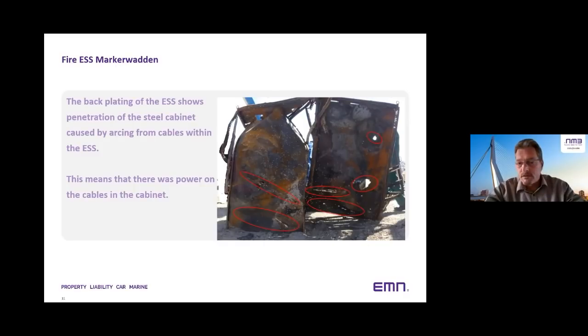This meant for us that there was power on the cable, either from the site itself or from the batteries, which we did not determine, because the solar panels were connected through the system to an inverter, and the communication between those units had not been well tested before. This was the second time they started up this energy storage source, and that's when it went wrong.